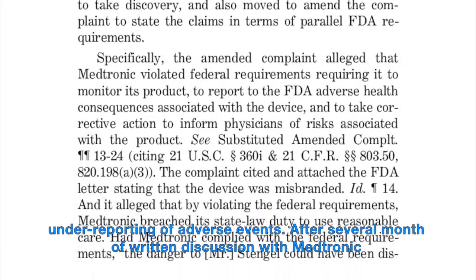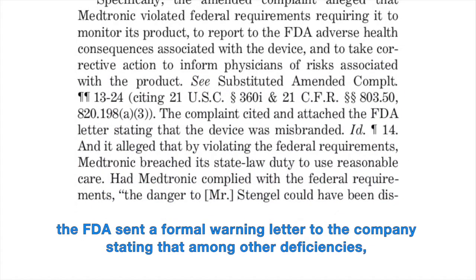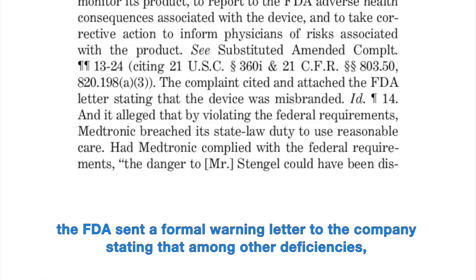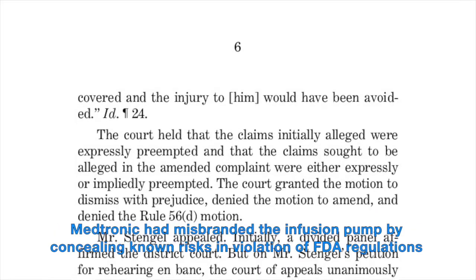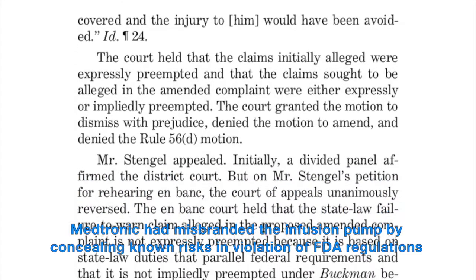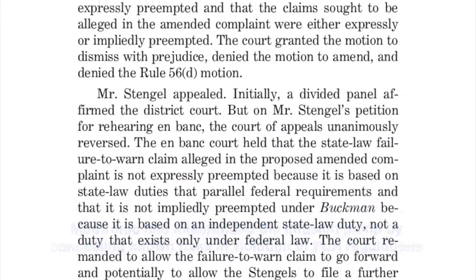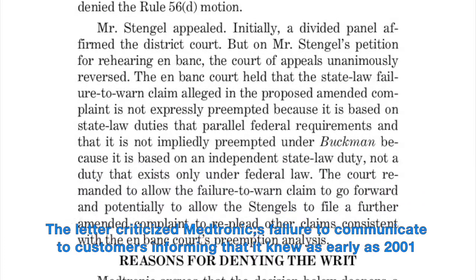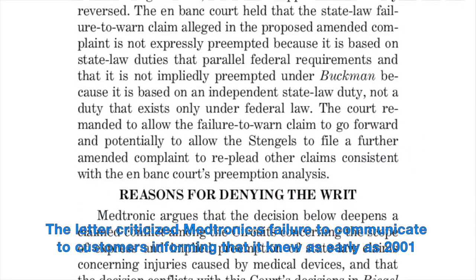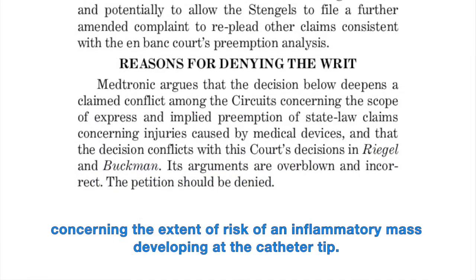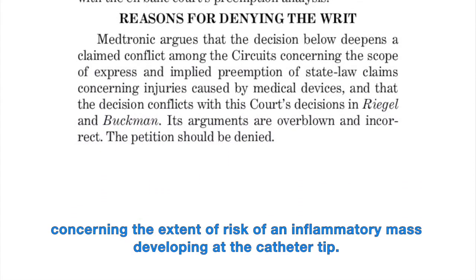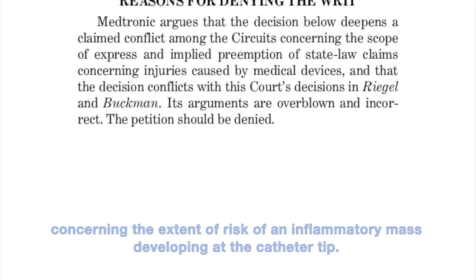After several months of written discussion with Medtronic, the FDA sent a formal warning letter to the company, stating that among other deficiencies, Medtronic had misbranded the infusion pump by concealing known risks in violation of FDA regulations. The letter criticized Medtronic's failure to communicate to customers, informing that it knew as early as 2001 concerning the extent of risk of an inflammatory mass developing at the catheter tip.